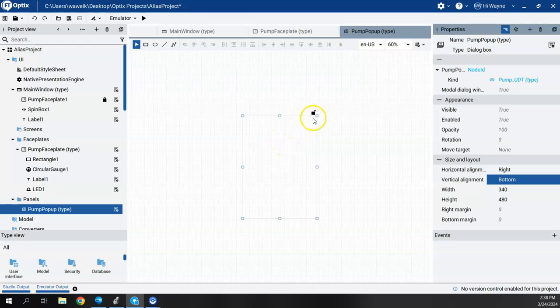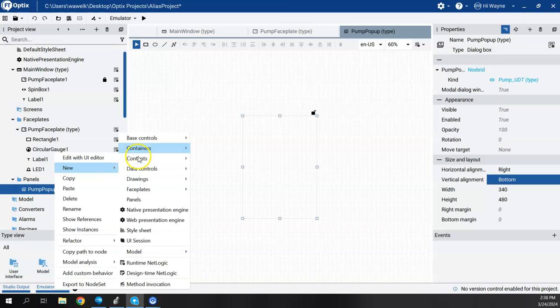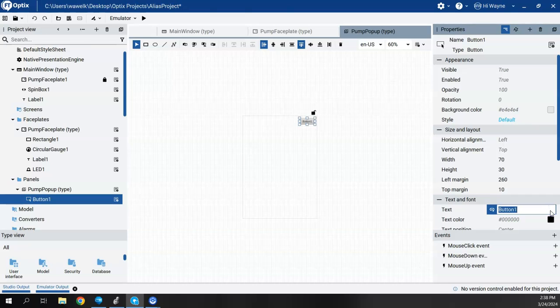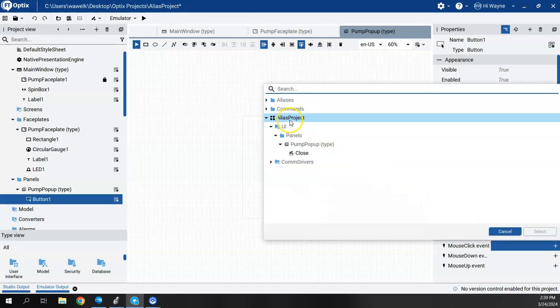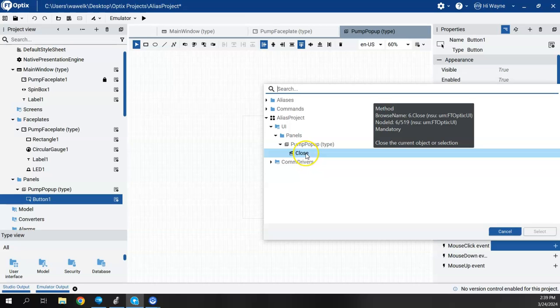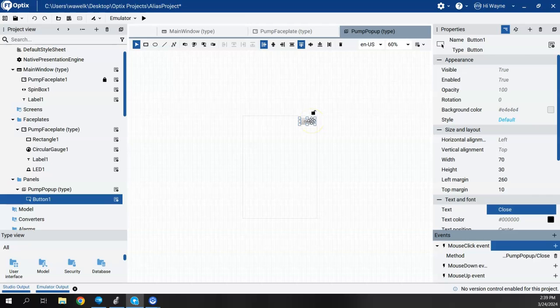Next, I want to add a push button in the upper corner to close the popup. I'll come to the pump popup, right-click, say new, base controls, and add a button. I'll stretch the button out a bit and change its name to close. The only thing I need to do is give it an event. On mouse click, I'll hit add new method. I can see my pump popup has the close method already available — I'll click close and say select. Now when I click that button, it will close the dialog.